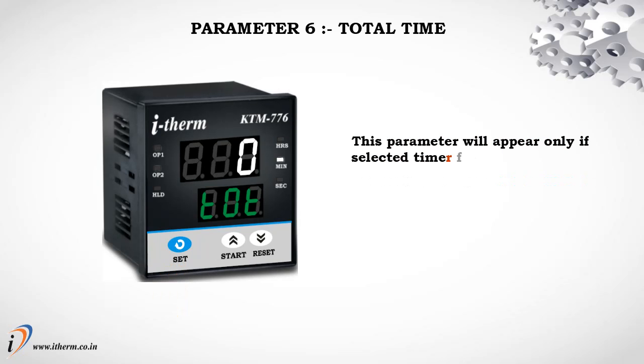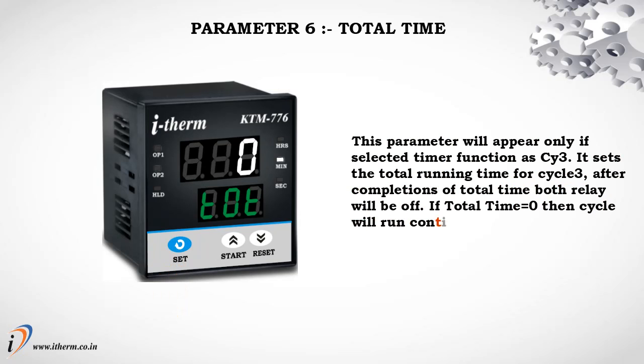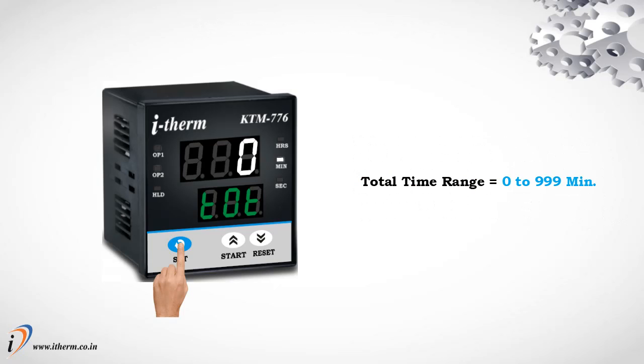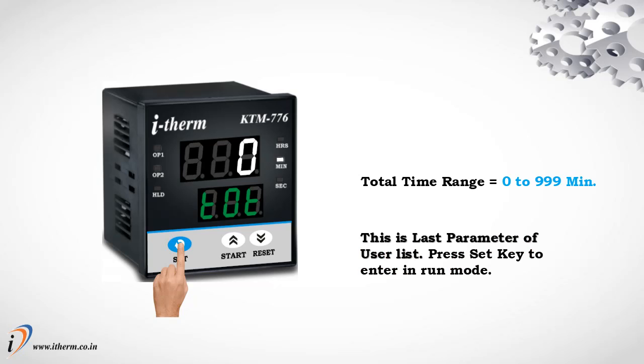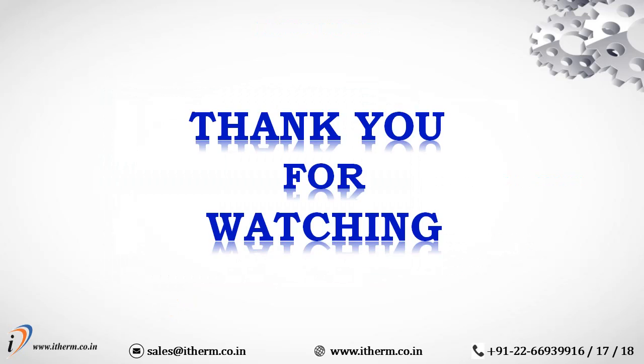Parameter 6: Total Time. This parameter appears only if the timer function is Cycle 3. It sets the total running time for Cycle 3. After completion of total time, both relays will turn off. If Total Time equals 0, the cycle runs continuously until a reset pulse. Total Time range: 0 to 999 minutes. This is the last parameter of the User List. Press Set key to enter Run Mode. Thank you for watching.